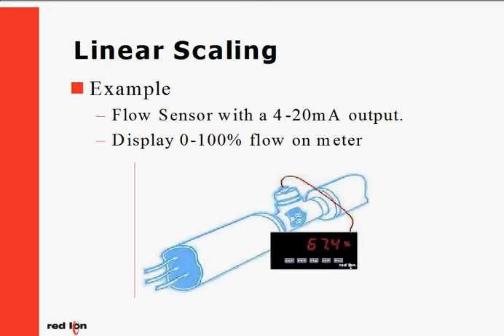Our example shows us having a flow sensor giving off a 4 to 20 milliamp process signal. Our meter then in turn needs to be scaled to read 0 to 100 percent on the display. The following steps will show us how to plug in the proper parameters to successfully scale this meter.